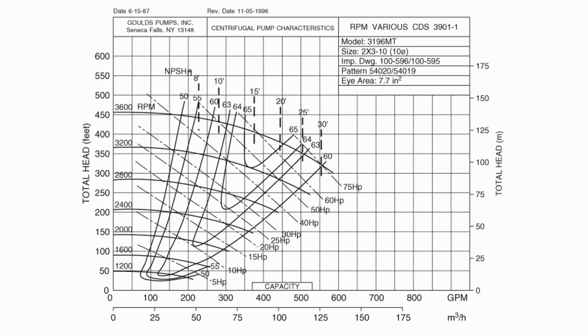Now, these numbers, 1,200, 1,600, 2,000, those are the rotations per minute. So if you have a certain pump and you're spinning that pump at 1,200 RPM, then this is its performance curve. Its cutoff head is 50 feet, and it decreases from there. The more flow rate you're trying to achieve with the pump, the less head it's able to provide. But if you pair that same pump with a different motor, and that motor is able to achieve 1,600 RPM, well then suddenly you've got a lot more head out of that same physical pump. And so the first thing I wanted to point out is just the different RPMs and what effect that can have on the pump head.